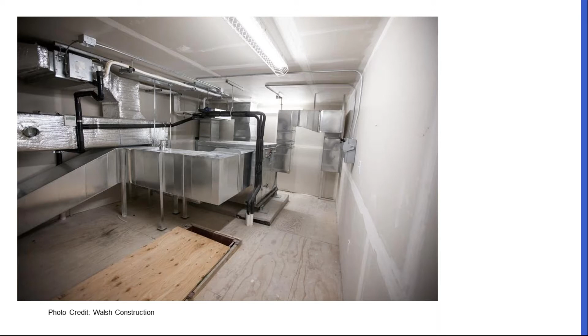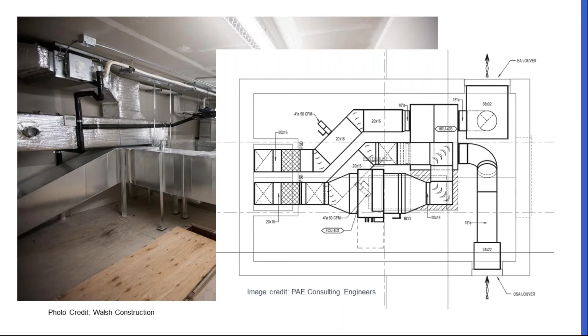What that allowed them to do is - I talked about how we don't have much cooling load, but Portland actually has approximately the same cooling degree hours as Boston does, dry bulb. They have dry summers, not hot humid summers. So the theory is we can put part of our heating and cooling load in the central ventilation system, dehumidifying the air with that little bit of dehumidification we need.